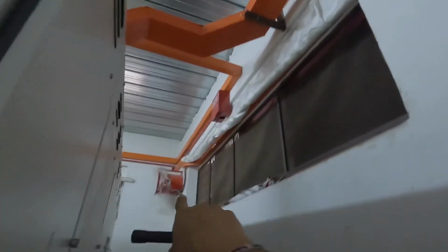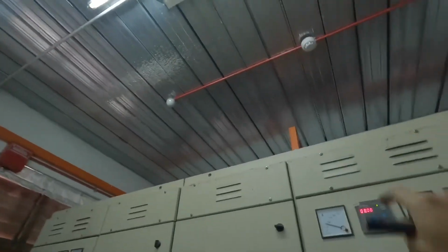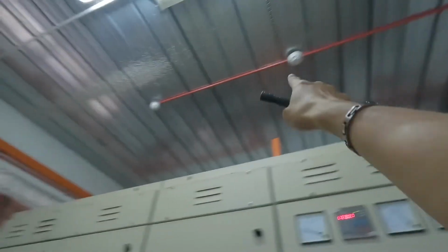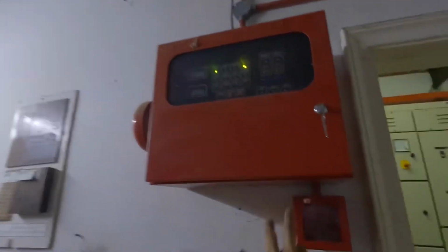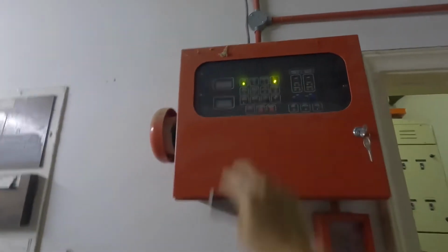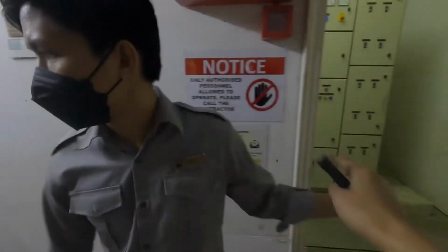Recommended to install. No burnt cable, no loose termination. Inside this LV room, there's not much big issue on the firefighting system. There's a fire curtain installed. The fire extinguishing system is in place. Let us have a look at the smoke detector. Smoke detector is in place. Heat detector is in place, no problem. And CO2 panel available, key available, in good condition. No problem. Only this one needs to be relocated to the side of the door.